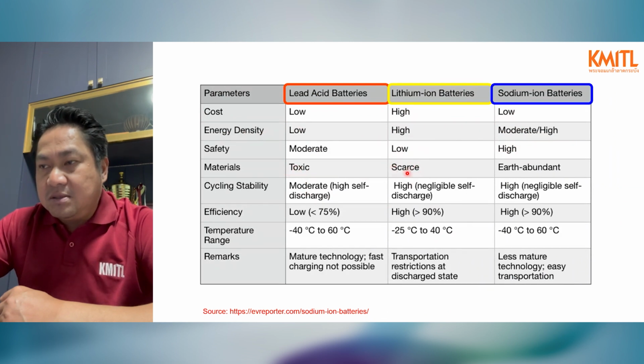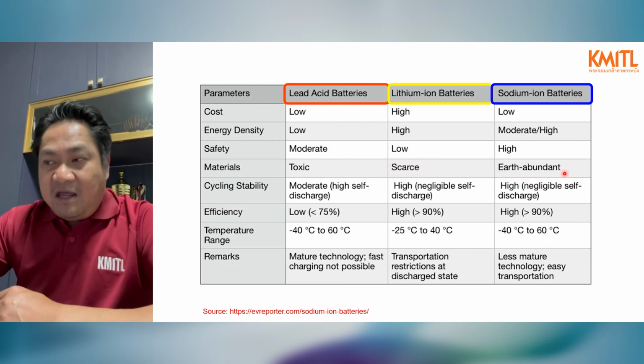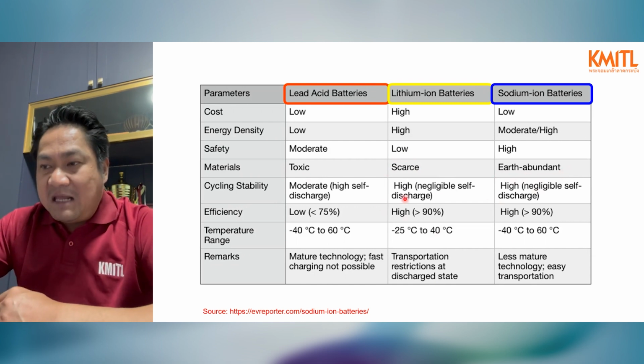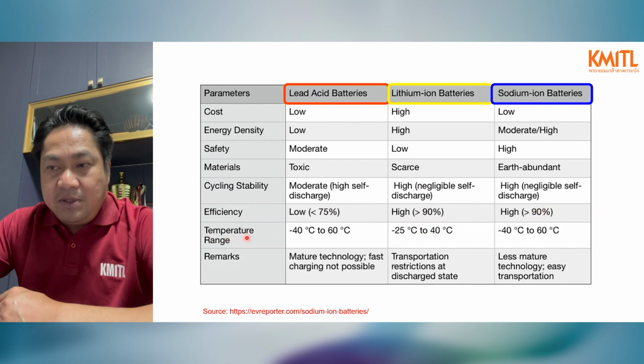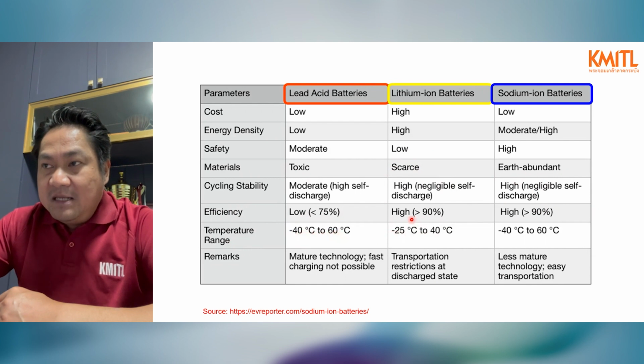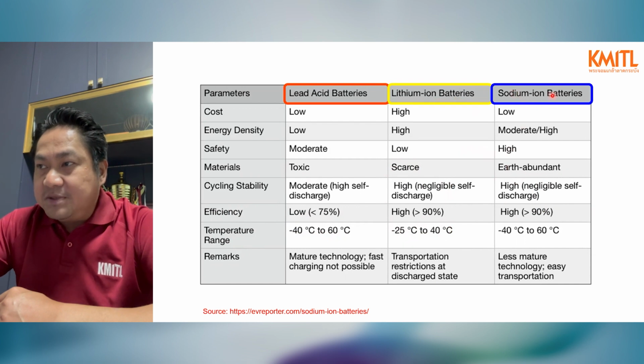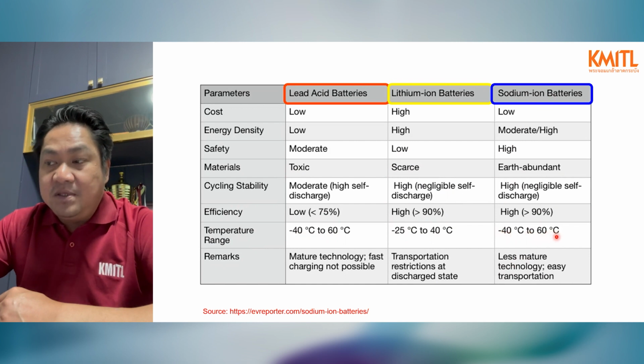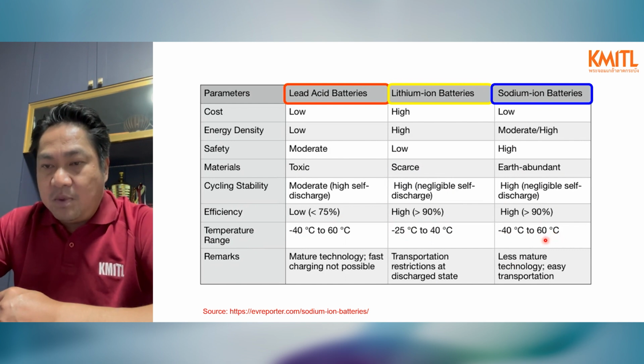This will be a scratch point: the sodium-ion battery is earth abundant, meaning it can be made cheaper in the future. Life cycle efficiency for lead acid is less than 75%, but for lithium it's more than 90%, similar here. For temperature range, lead acid is minus 40 Celsius to 60 Celsius, lithium-ion is minus 25 to 40 Celsius, but the sodium-ion battery can range from minus 40 up to 60 Celsius. That means in the future we may not need extra temperature-controlled rooms for them.